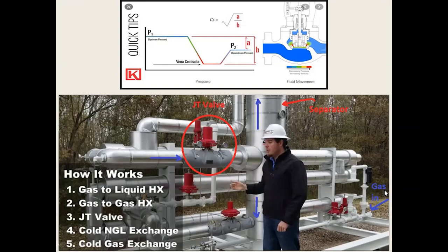Here is what I expect: the gas in, and it goes in through the gas-gas heat exchanger, with several passes to heat exchange, and then here is the upstream of the valve, and here is the downstream of the valve, and this I considered as the low temperature separator. The liquid hydrocarbons get down, and the natural gas, after separating the heavy hydrocarbons, goes up the separator.